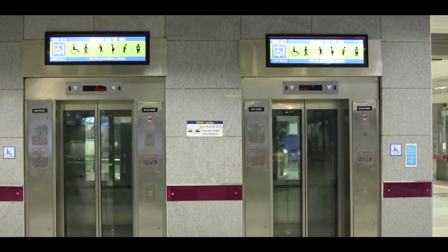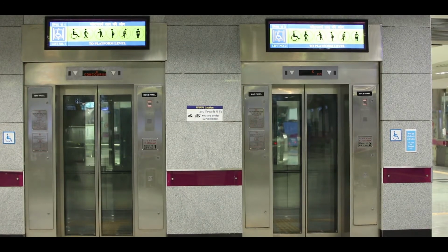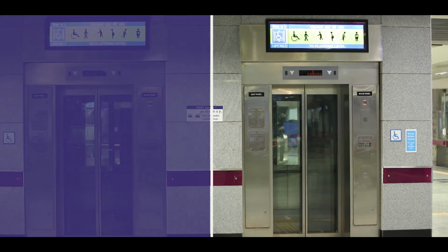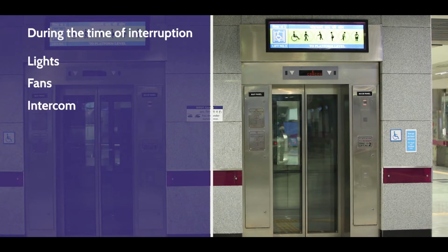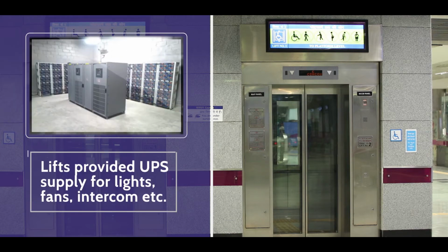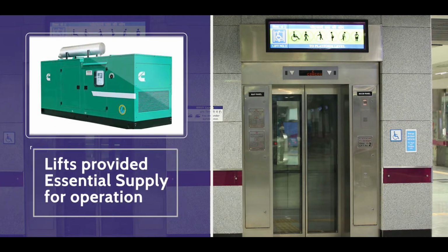While traveling in a lift, in the unlikely event of power supply failure, it is desired that during the time of interruption, the lights, fans, intercom and control system should function. Therefore, lifts are provided with uninterrupted power supply. In addition to uninterrupted power supply, in case of power supply breakdown, it is also required that the lift should complete its travel to the next landing in order to avoid any trapping, and hence the lifts are provided with essential power supply.